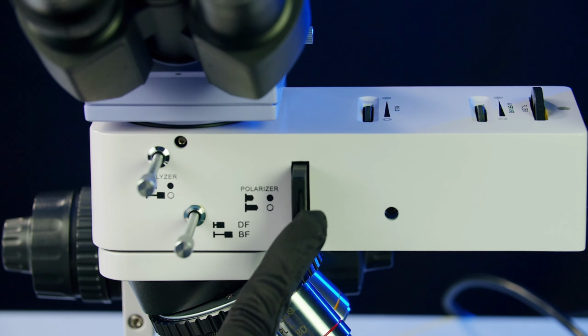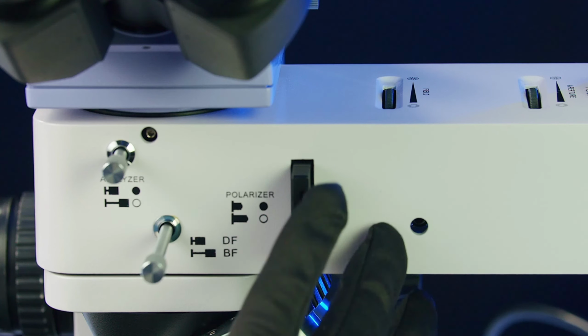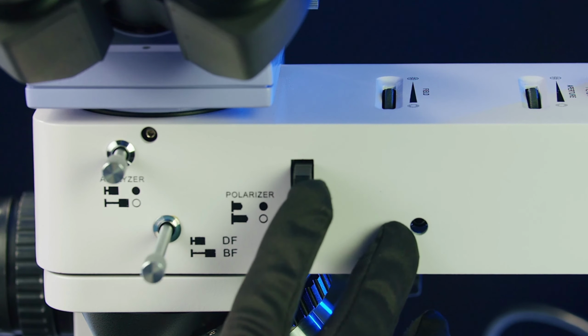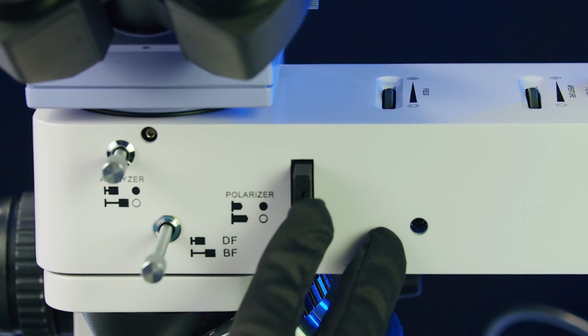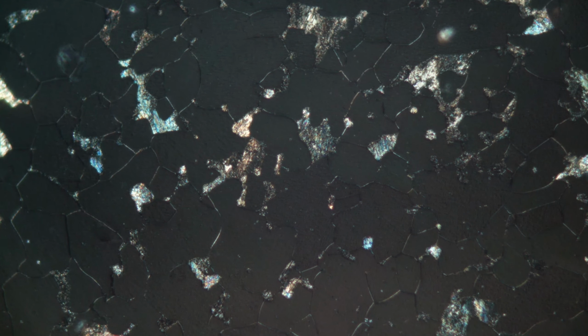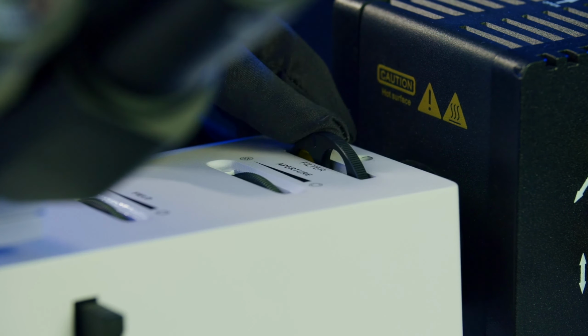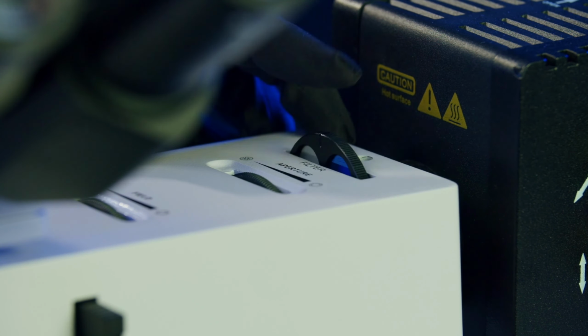To observe objects in polarized light, a polarizer and analyzer are introduced into the optical path. The polarizer rotates 360 degrees, providing precise adjustment of polarization and contrast. By rotating the polarizer, the required position of the polarization devices is set, and then the brightness of the illumination is adjusted. Light filters are used to optimize image contrast for different types of specimens.